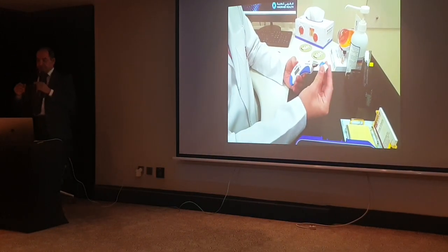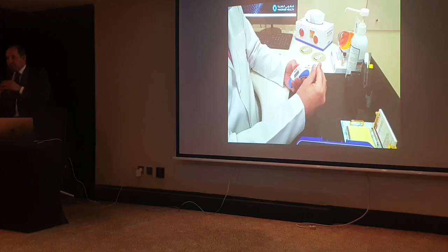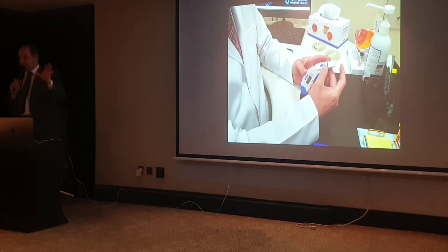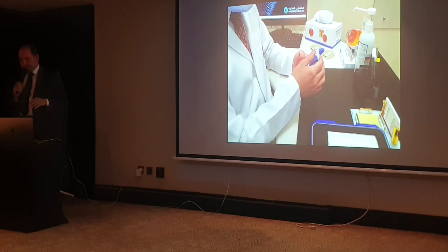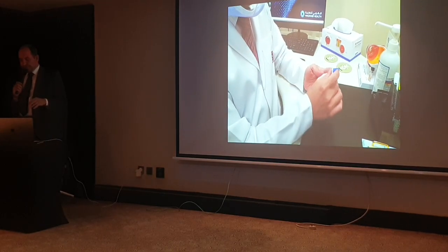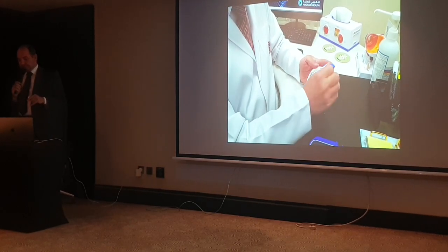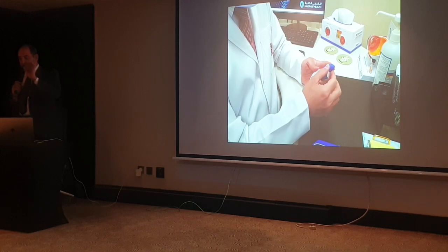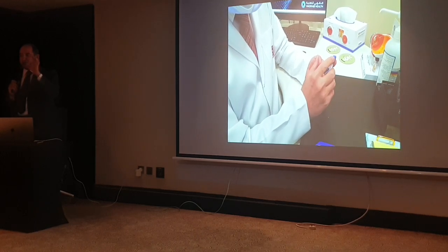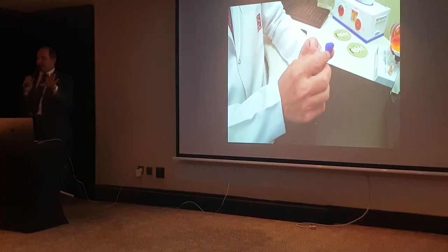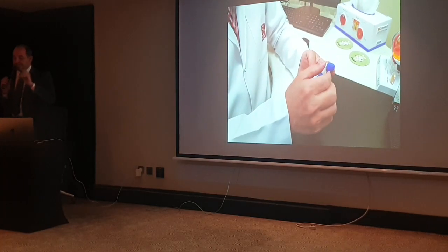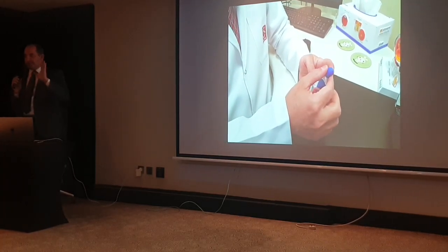For the Tonopen, look at the sleeve and how we are putting it, because there is a problem with measurement with the Tonopen. Fine corrugation at the tip. If you have the fine corrugation, you are right. If you don't have it, this means it is overstretched like this.